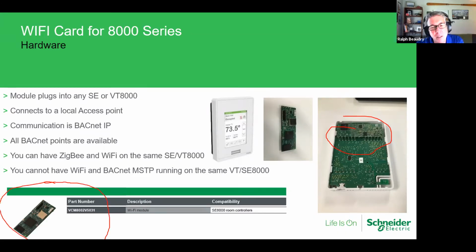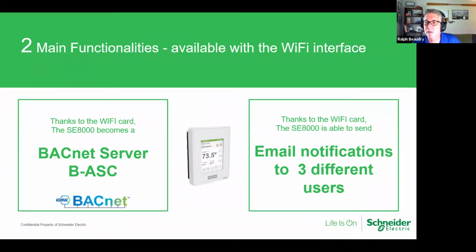What that gets you is Wi-Fi enabled BACnet. I connect it to an access point, and at that point I'm communicating Wi-Fi down to my thermostat, but the information is BACnet IP. So I can pull that thermostat into my network if I have a network-level controller on that network, and it's just a BACnet IP device. All of the BACnet objects you'd expect to see in the 8000 are available. So now with Wi-Fi, the 8000 becomes virtually a BACnet server.